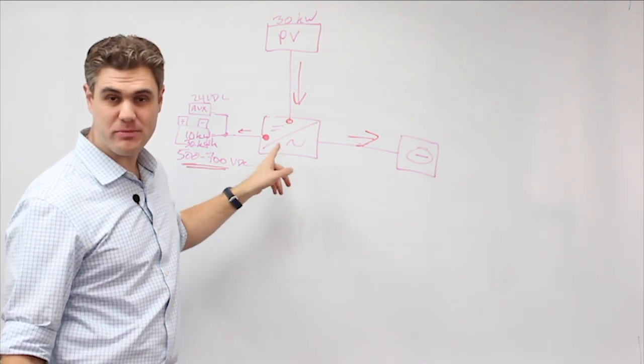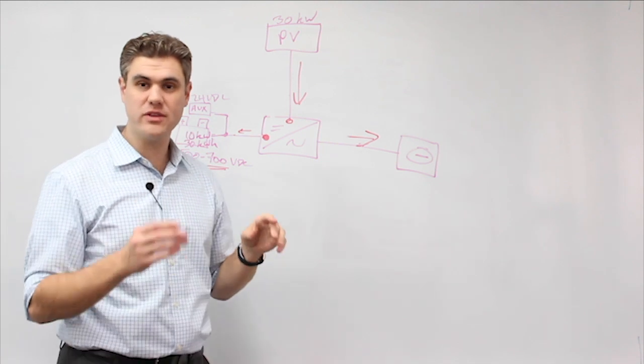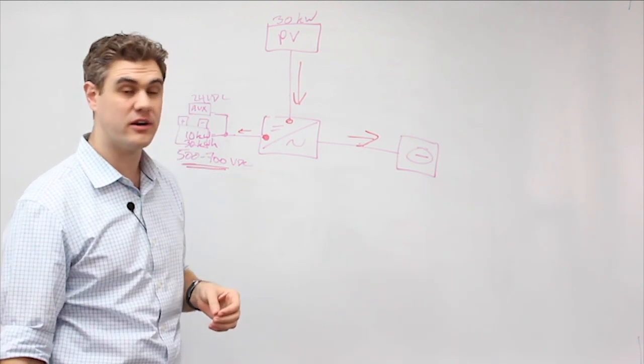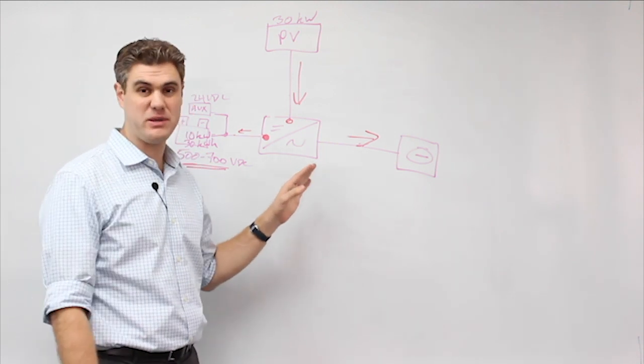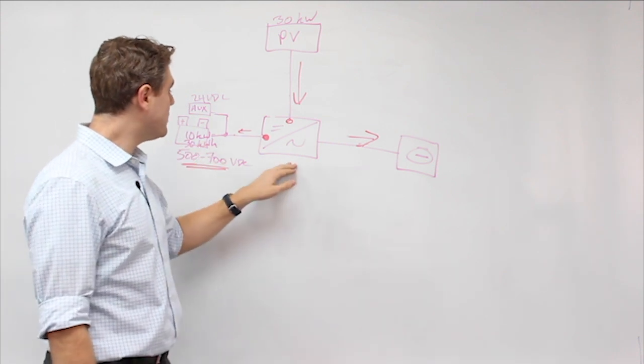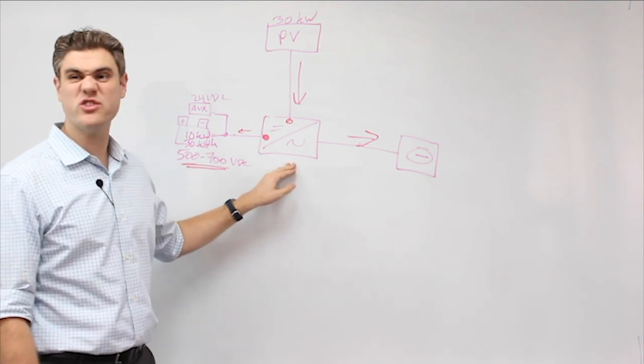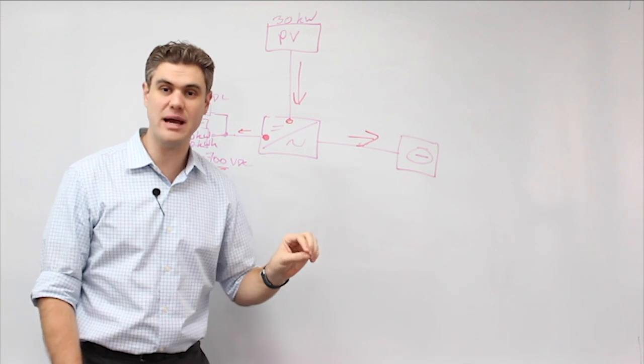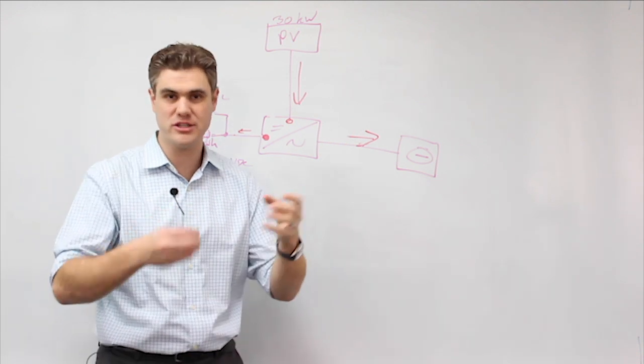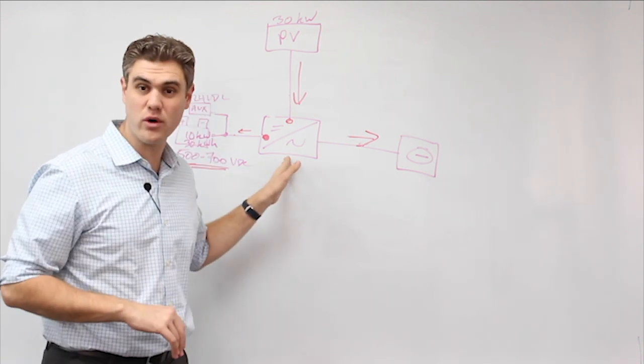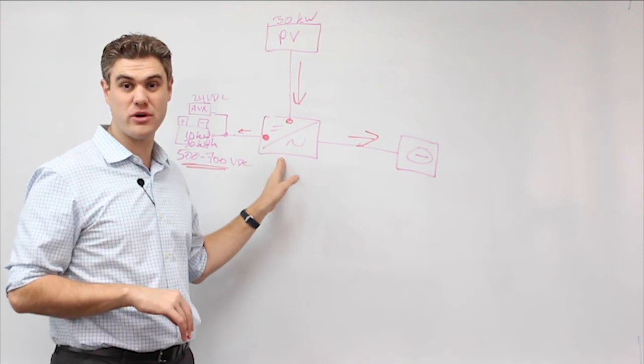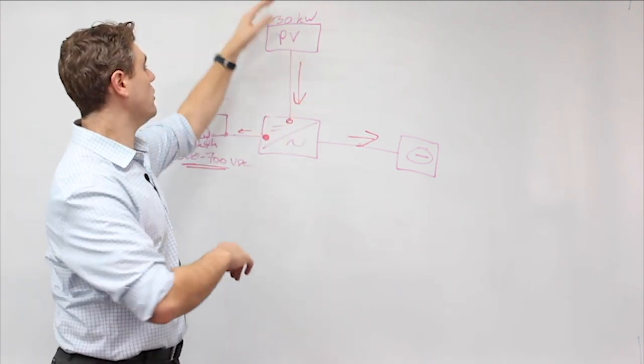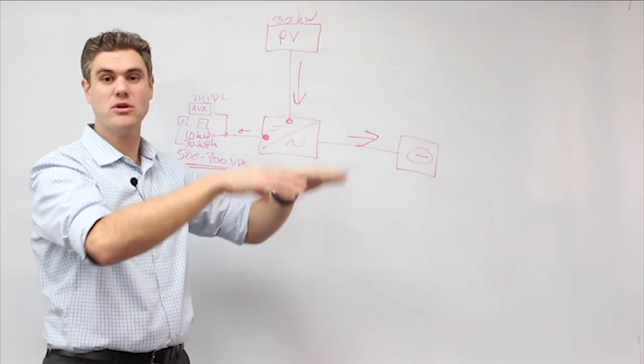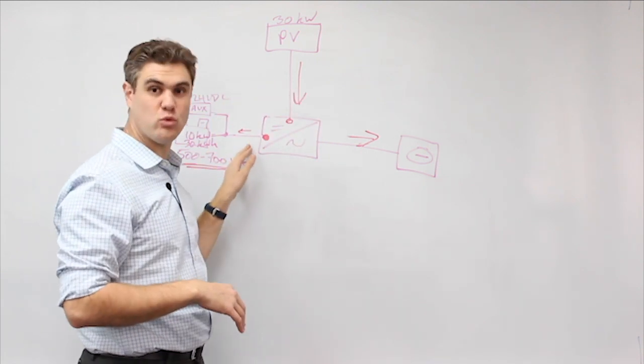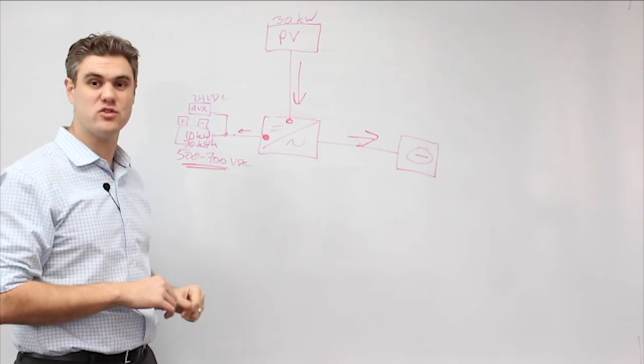And when you make that adjustment in the inverter, one of the really critical things here is the regulatory process, because that change in the firmware of this inverter is something UL or a third-party testing laboratory, an NRTL, Nationally Recognized Testing Lab, can test for. They can actually put this in a laboratory and test, when solar is at varying power levels, does it actually switch off this battery? Does it actually do its job?